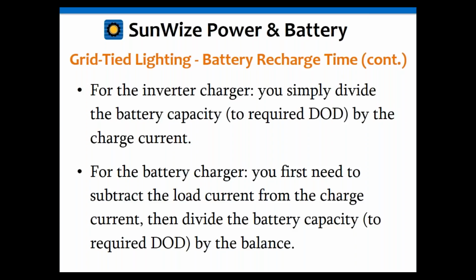So I think that's the big key there, that a lot of people forget about that. They're thinking, oh, I have a 25 amp charger, I can charge my battery at 25 amps. You can't, because remember, part of that has to go to support the load first, then the remainder needs to go to the battery. That's something you should think about when sizing a charger. If you have maybe a larger load, like a 20 amp load, and you have a 25 amp charger, then only 5 amps can go to recharging the battery, and that might take a lot longer. It may take more than 24 hours to recharge your battery, and that may not be acceptable to you. You may want to have the battery charged in 8 to 12 hours, so you may want to go to a bigger battery charger because of that. Now, if you're okay with taking 24 to 40 hours or more to recharge your battery, then that may be just fine. So it's just something else to consider as you're selecting your components and looking at the capacities of the battery and the current of the charger that you have.